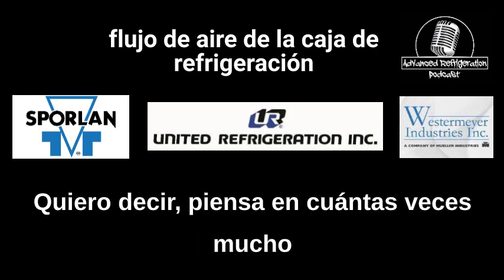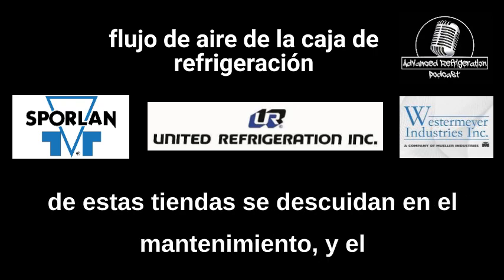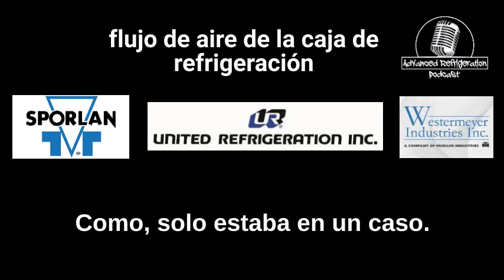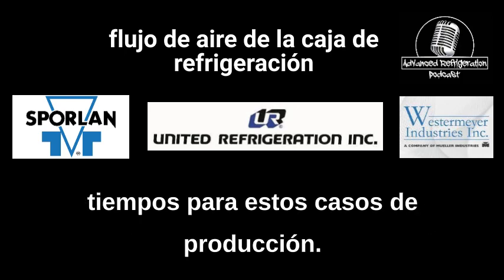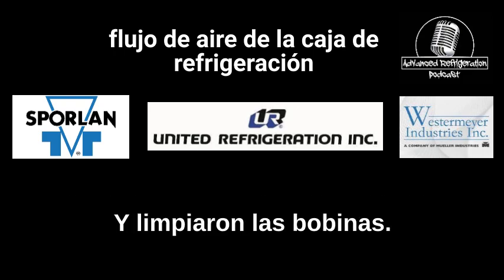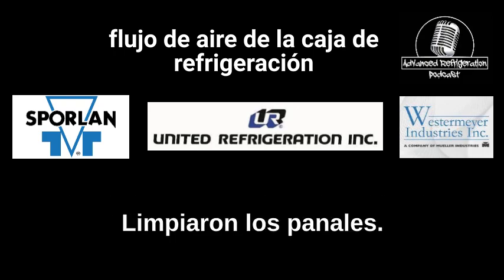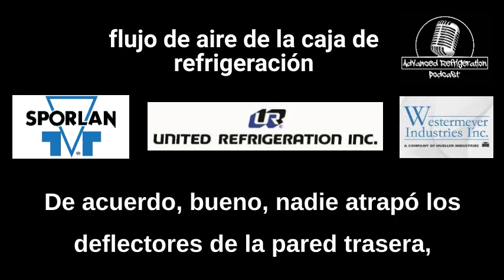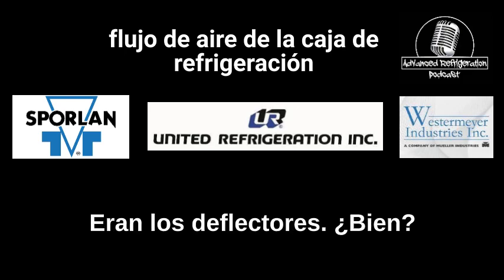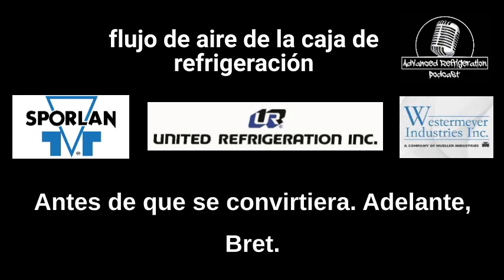I mean, think about how many times a lot of these stores get neglected on maintenance, and the baffles get missed in the back walls. Like I was just on a case. We were out there like 6 times for these produce cases. They continue to ice up, nonstop problems. And they cleaned the coils. They cleaned the honeycombs. They were filthy. Okay. Well, nobody caught the back wall baffles. And they were in a weird spot. They were on the upper side. They were the baffles right before it turned.